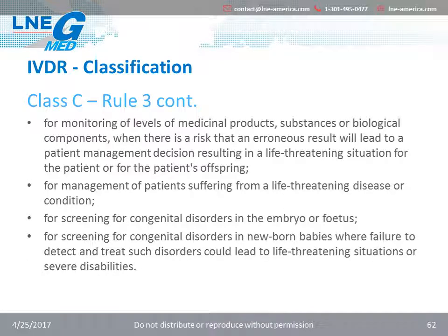Class C, Rule 3, for monitoring of levels of medicinal products, substances, or biological components when there is a risk that an erroneous result will lead to a patient management decision resulting in a life-threatening situation for the patient or the patient's offspring. For management of patients suffering from a life-threatening disease or condition. For screening for congenital disorders for the embryo or the fetus. And for screening for congenital disorders in newborn babies where failure to detect or treat such disorders could lead to life-threatening situations or severe disabilities.